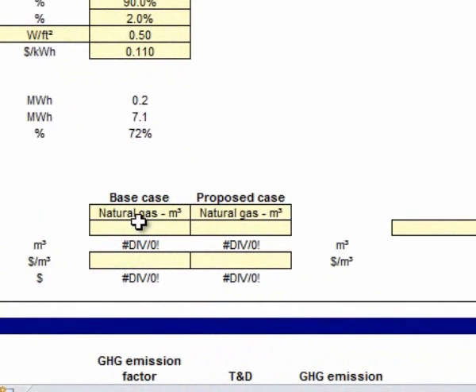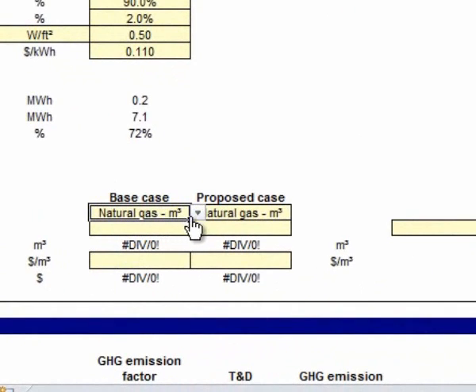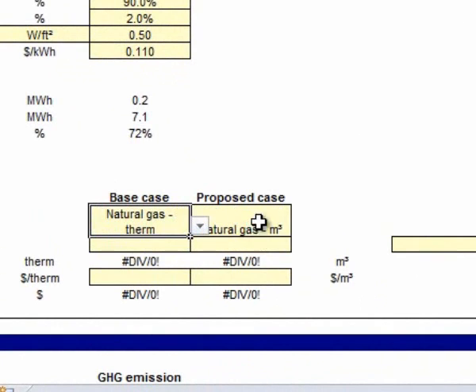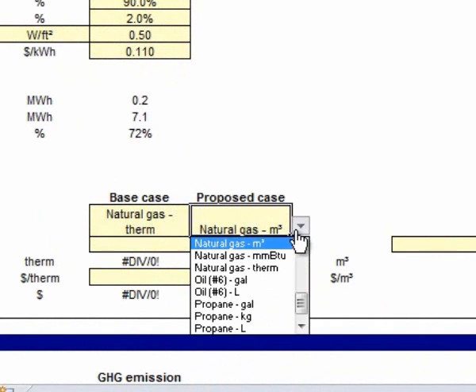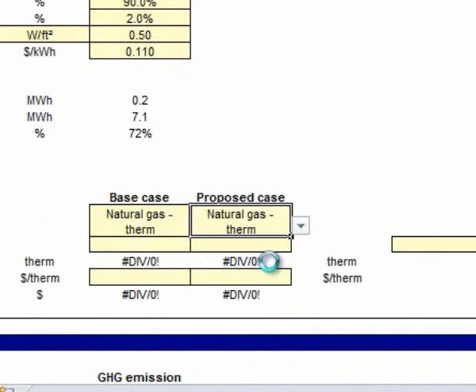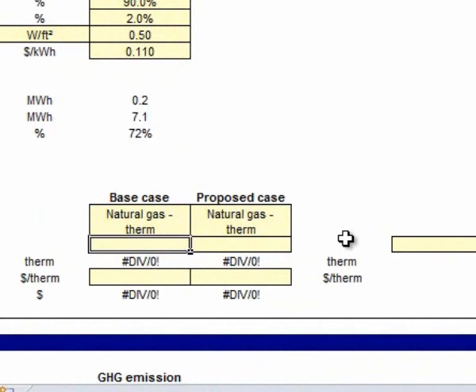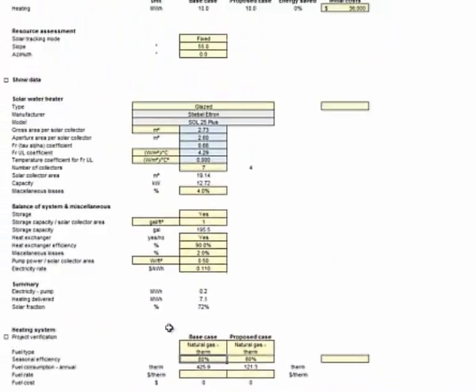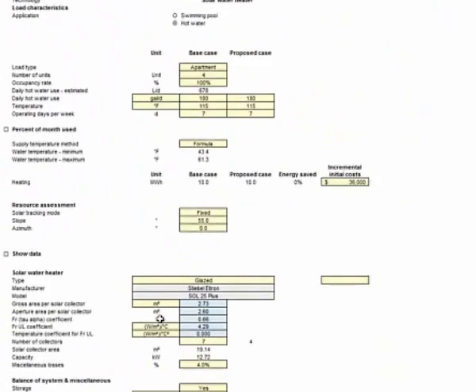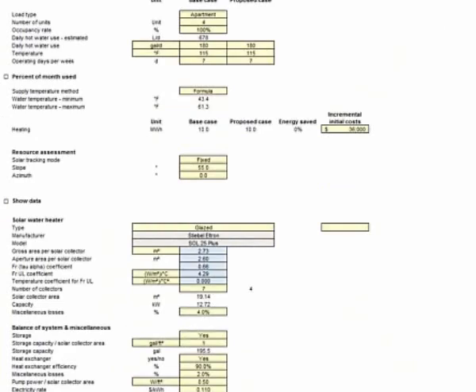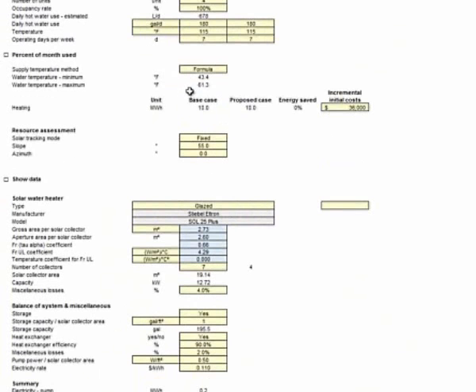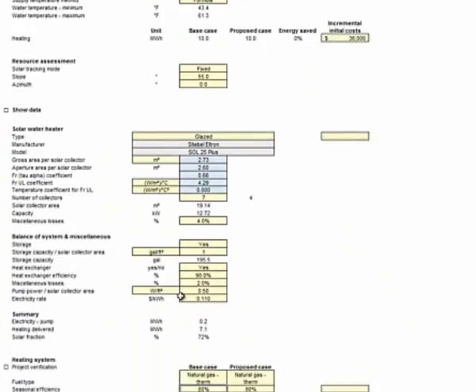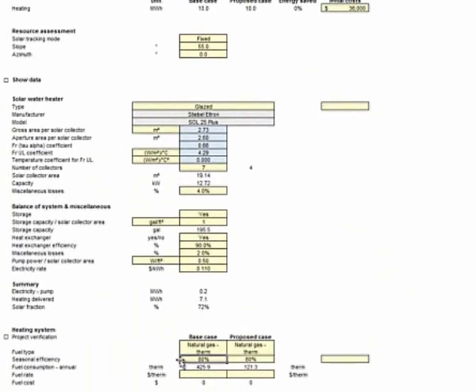Now both of them are going to use natural gas. So let's convert that to natural gas into therms and natural gas into therms because our gas bills here in central Illinois are based upon therms. Let's leave this both at 80%. The seasonal efficiency is between how much of the cold water comes in. And remember on the page one, so we said that the water coming in is 43 degrees in the wintertime, 61 degrees in the summer. And then we've got storage. We've got some other things.